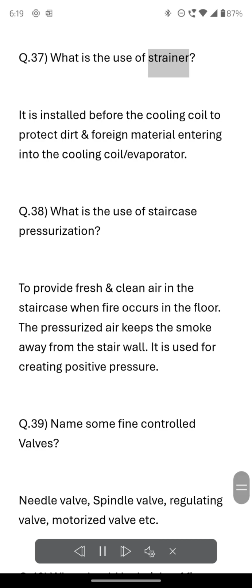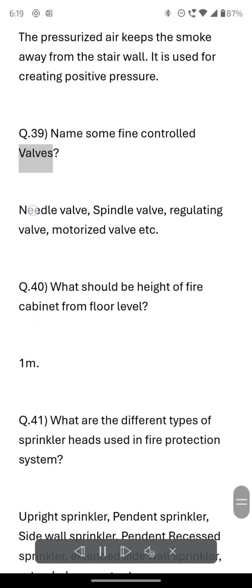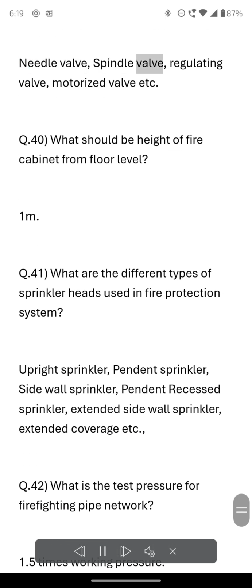Q.37 What is the use of strainer? It is installed before the cooling coil to protect dirt and foreign material from entering into the cooling coil evaporator. Q.38 What is the use of staircase pressurization? To provide fresh and clean air in the staircase when fire occurs on the floor. The pressurized air keeps the smoke away from the stair wall. It is used for creating positive pressure. Q.39 Name some fine control valves. Needle valve, spindle valve, regulating valve, motorized valve, etc. Q.40 What should be height of fire cabinet from floor level? 1 meter.